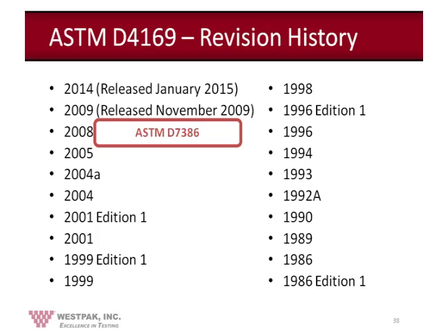Going back to the revision of ASTM D4169: in the 2008 revision, another performance standard was introduced — ASTM D7386. ASTM D7386 is a relatively recent package integrity test standard. Many old-timers often wonder why this procedure required a separate document rather than simply another distribution cycle. What really happened was an attempt to modify distribution cycle 13 and add some elements to it. It basically does the same thing as D4169 but is geared toward the specific requirements of smaller parcels, such as medical devices and pharmaceuticals.